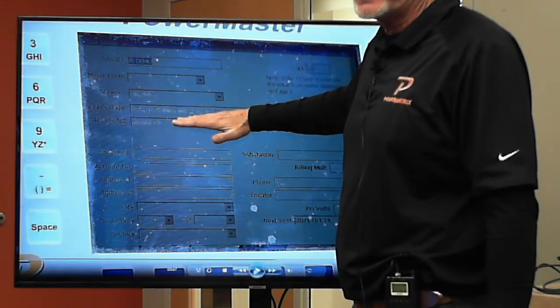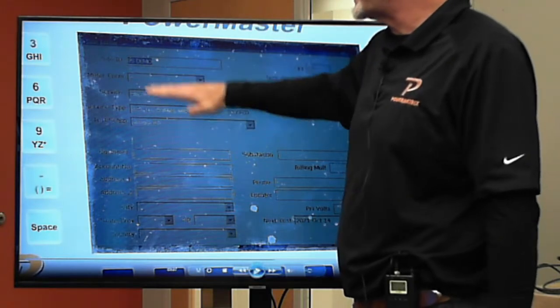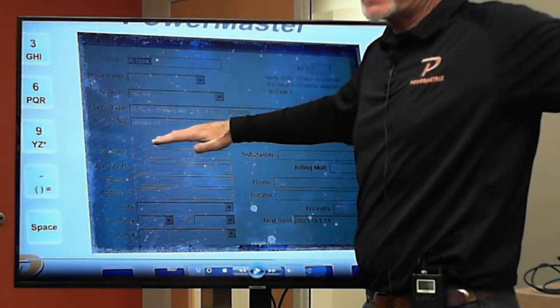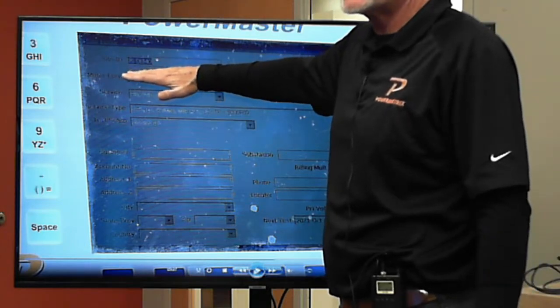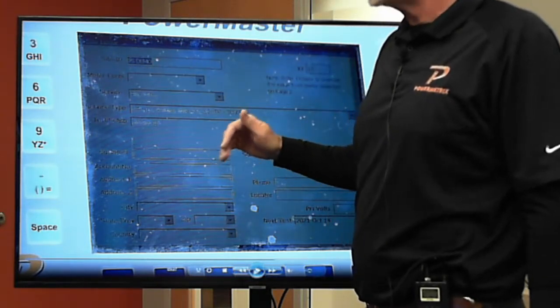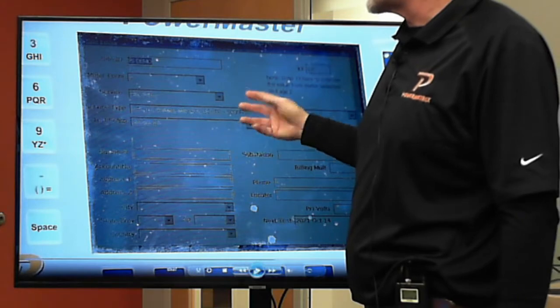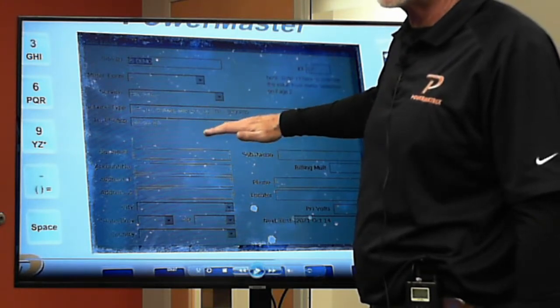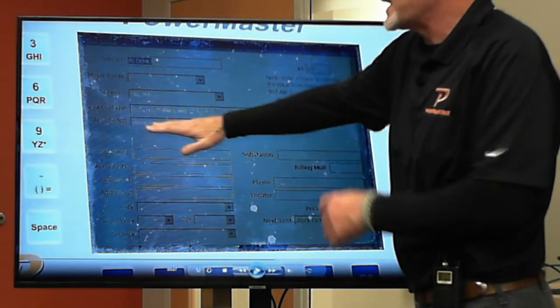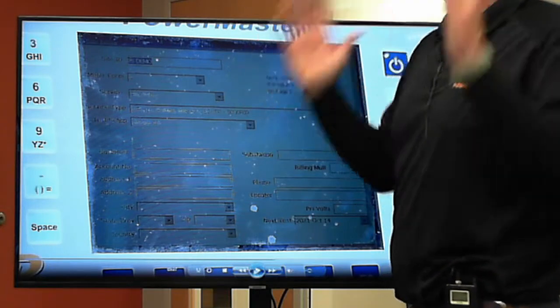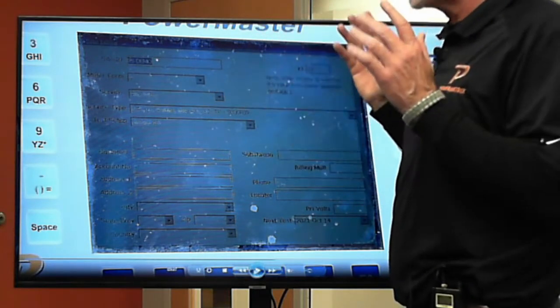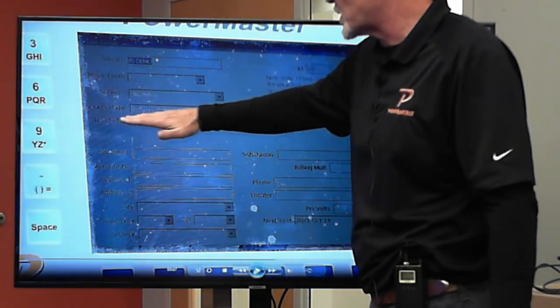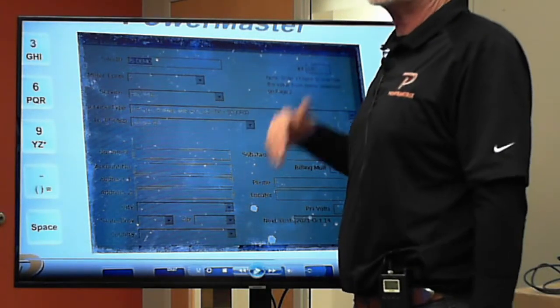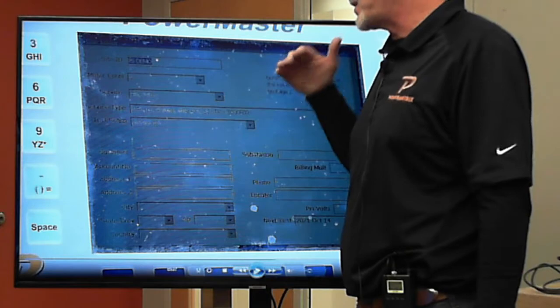what it defaults to. When you choose different sites, we tested an 8S site in the previous webinar, and when we chose that 8S site, it defaulted to, I believe, 2 voltages, 3 currents, but whatever it defaulted to was not correct for it. You had to drop down and pick out the correct service type. So you need to make sure that you're pairing up the correct service type with the service that you're actually testing, or it's going to be a pain in the rump.